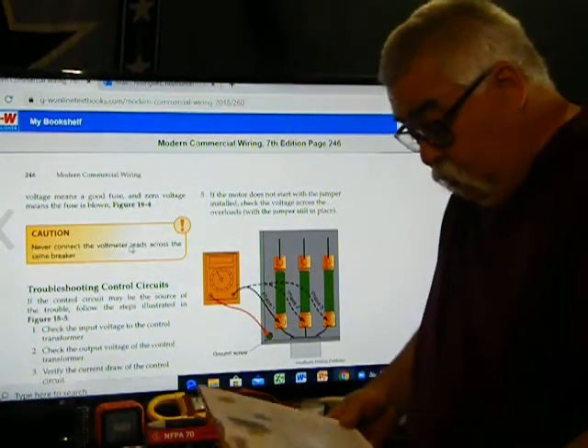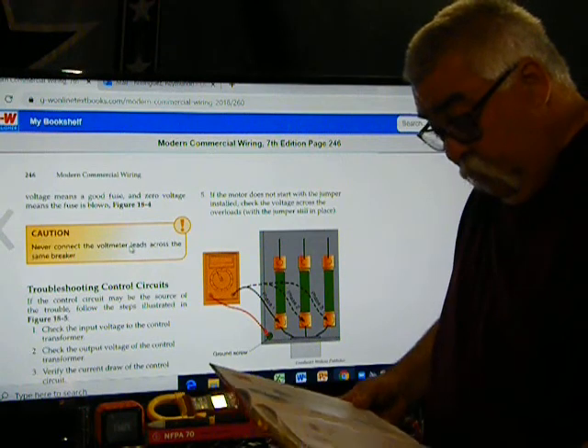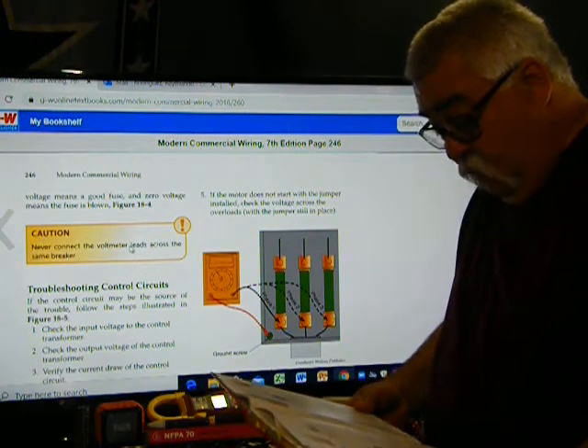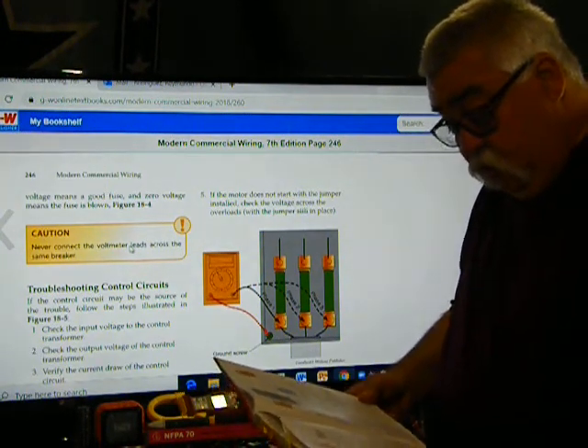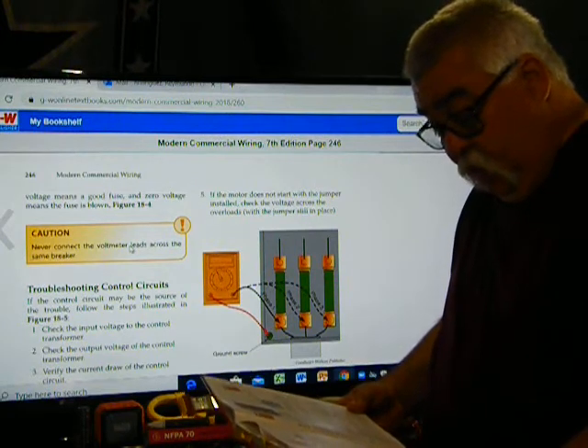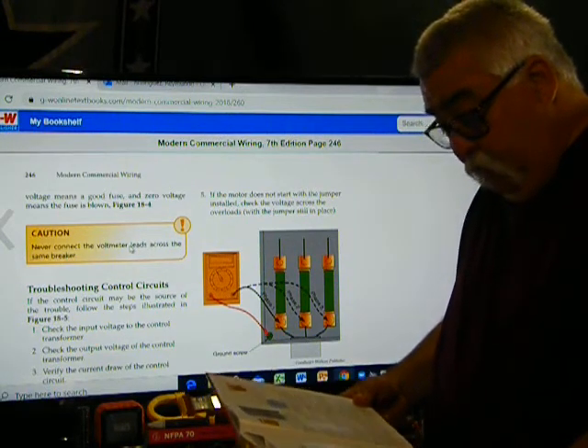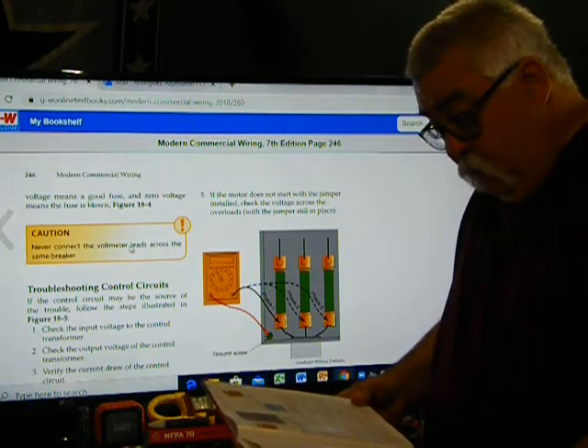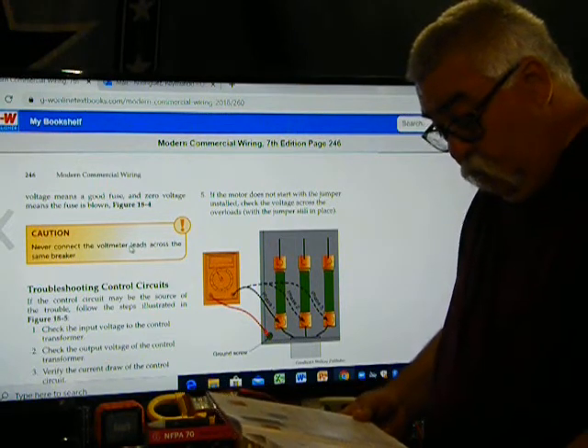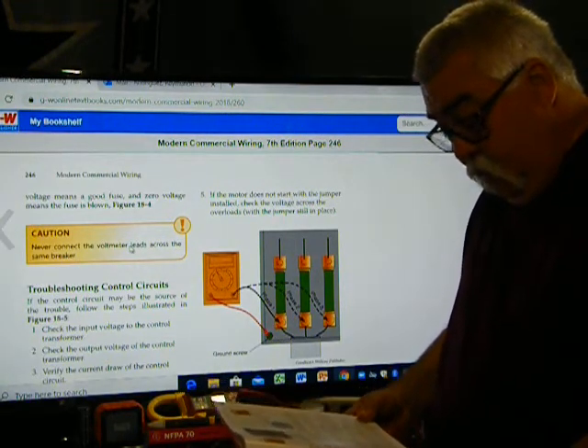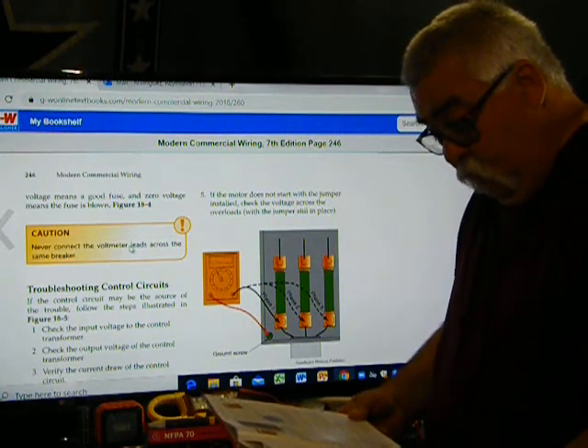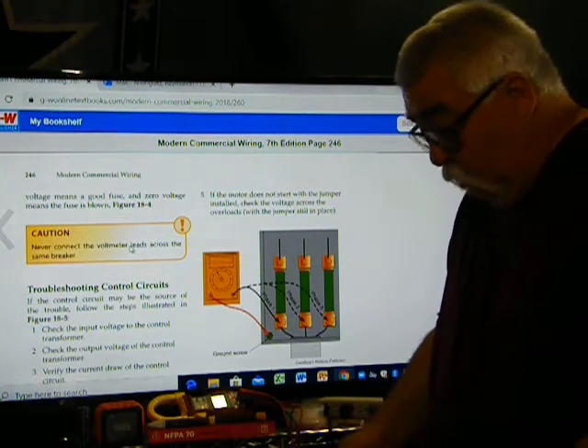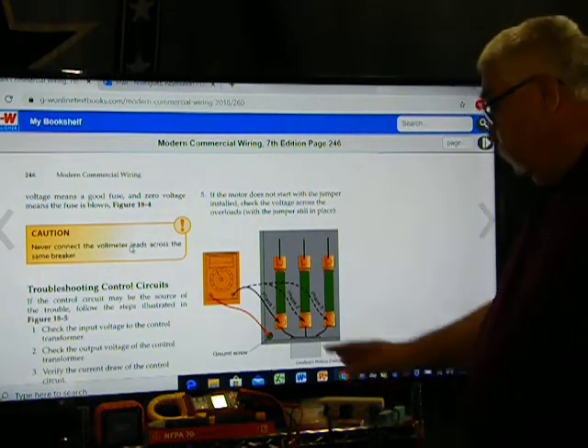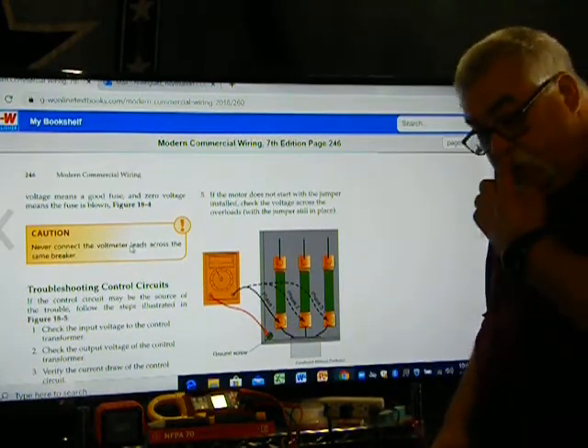So unbalanced voltage at the power source is detrimental to the motor windings. Unequal voltage can cause the current to be several times higher relative to the voltage imbalance in the motor and heat the motor windings. This reduces the torque, causing vibration and eventually bearing or winding damage. Voltage should be checked with a voltmeter for unbalanced voltage.